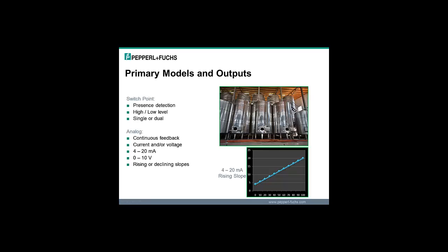The two basic primary output types for ultrasonic sensors. There's switch point output, which is basic. Is the box there? Is the box not there? Is the level too high? Is the level low? And a lot of our sensors will have single or dual switch point outputs. So that's really the proximity mode. Works just like a proximity sensor. Is the target there? Is the target not there?